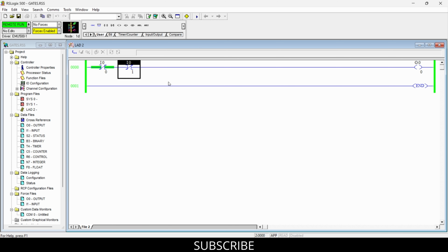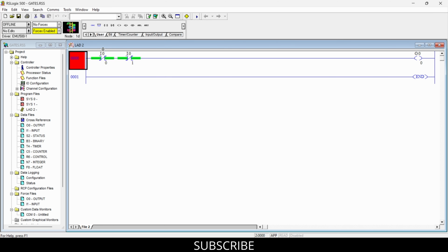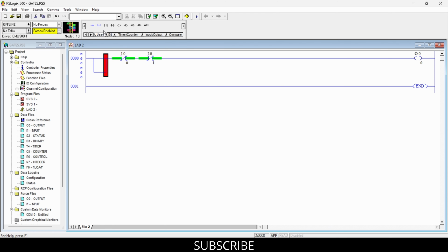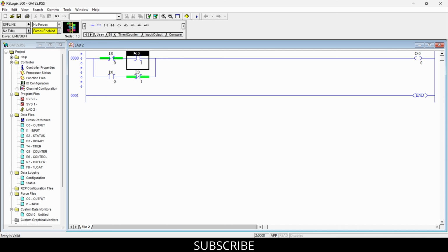So let's move further to our next logic gate, which is a little bit complex, but I will explain it in the easiest way possible. Let's create the XOR gate in ladder diagram. To create the XOR gate in ladder diagram, we need one branch instruction here. So this is the ladder depiction of the XOR gate. There are two inputs which are used simultaneously, NC and NO as well. You can see here I have used I:0.0 for our NC contact and NO contact as well, and I:0.1 for NC contact and NO contact as well. So this is how you can create the XOR gate in ladder diagram.